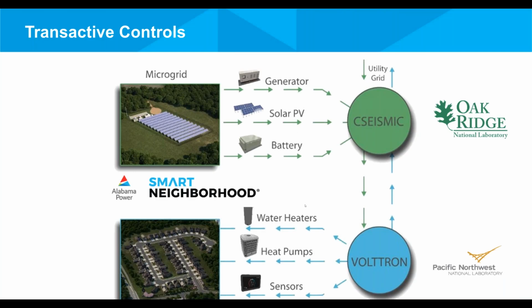Now, to talk about the transactive control aspect of this project, well, I've talked about SEISMIC already. SEISMIC is used to control the entire microgrid. For the microgrid, the different components have their own individual controller. The generator has a DICE controller. The solar PV has an SMA cluster controller. And the battery, we use PowerSecure's algorithm on a Siemens PLC. And all of that is being controlled by SEISMIC. Now, for the smart homes, there's a program developed by Pacific Northwest National Lab called VOLTTRON, and that is used to control the water heater, the heat pump, and all the other sensors in the smart homes. Now, both SEISMIC and VOLTTRON talk together in order to coordinate the operation of the microgrid and all the circuits in the smart homes, and also together they're able to create that transactive control that allows interaction between the utility grid and individual homeowners, as well as between the utility grid and the microgrid.